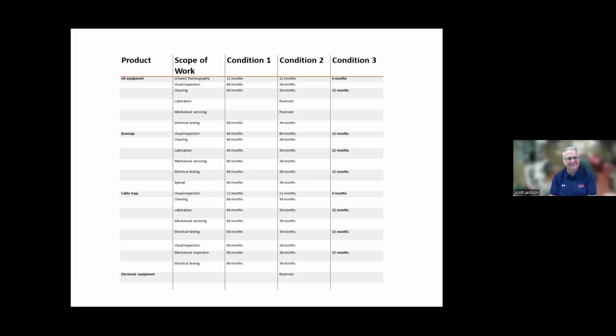So this is the table of 9.2.2. We only included the first page of the table because it goes on for 13, 14 pages, it actually takes up most of NFPA 70B. If you look at the top line, it says all equipment requires infrared thermography, regardless of whether it's condition one or two, and it mandates infrared scanning once every 12 months.